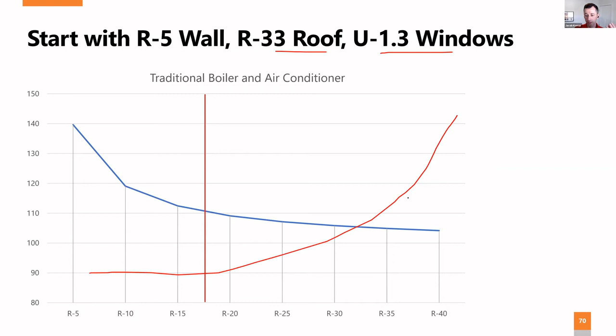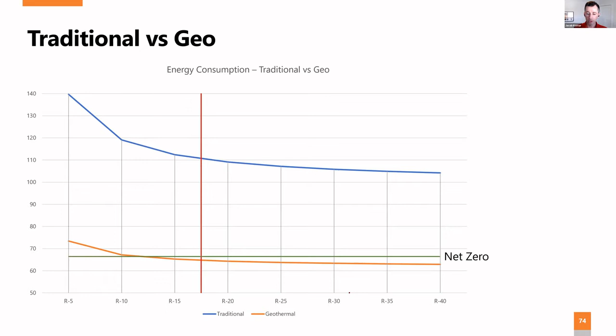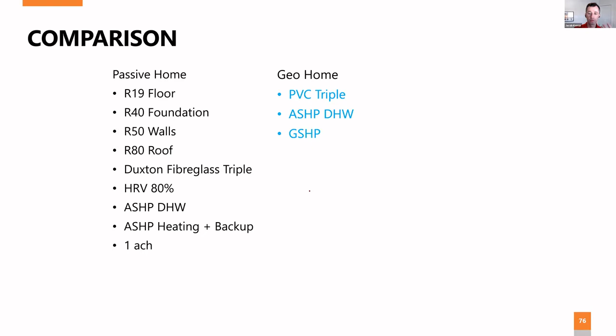If you attach a geo system, because you're dividing that load by 4, that curve is even flatter. So what we're finding is that with geo systems, upgrading the envelope has almost no financial benefit. I'm not saying you wouldn't want a better envelope for thermal comfort — I personally would, since our wall systems are pretty bad — but it means you can optimize for buildability and comfort instead of chasing an R40 or R50 target that's hard to build. We can reach net zero with much more conventional envelopes, and the comparison between the two approaches is staggering in terms of convincing people to actually do this.